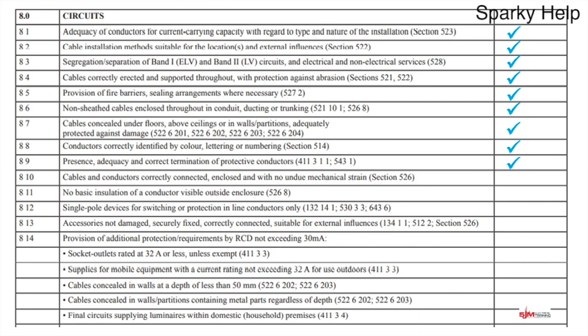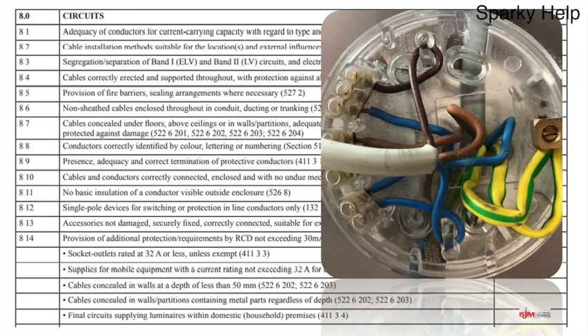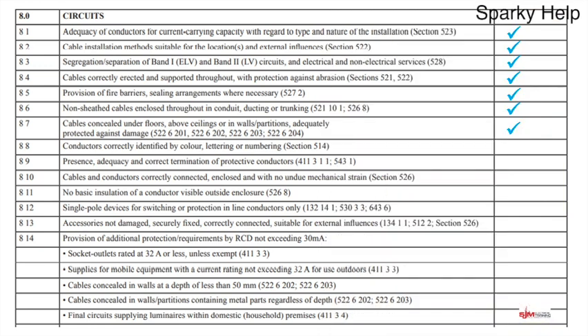Cables and conductors correctly connected, enclosed, and with no undue mechanical strain. No cables too tight to bend — keep within the bending radius — and all connected correctly as per manufacturer's instructions. If you've got cord grips, looking back at that ceiling rose you can see the flex is round the cord grips taking the weight, so you're making sure that is the case, and likewise in the lamp holder, that they're not supported by the terminations. Hopefully that's a tick.